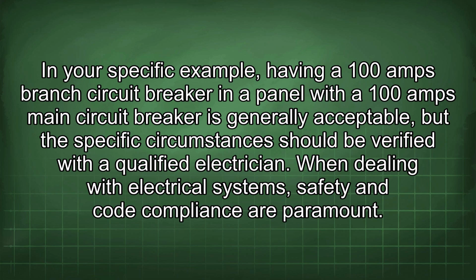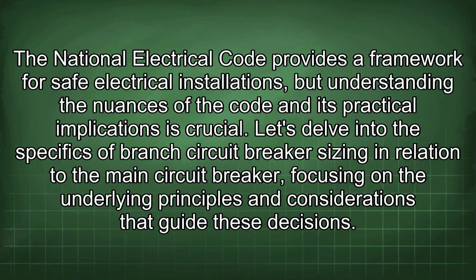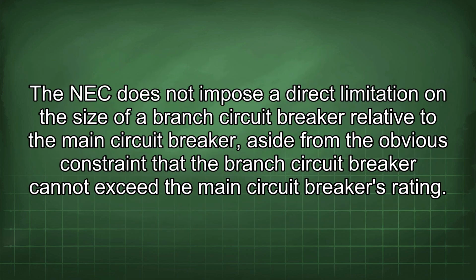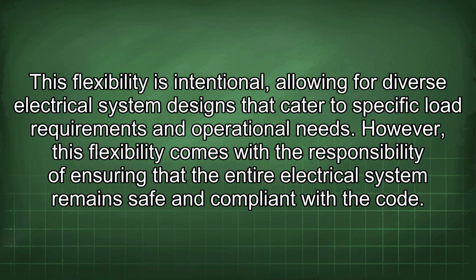When dealing with electrical systems, safety and code compliance are paramount. The National Electrical Code provides a framework for safe electrical installations, but understanding the nuances of the code and its practical implications is crucial. Let's delve into the specifics of branch circuit breaker sizing in relation to the main circuit breaker, focusing on the underlying principles and considerations that guide these decisions. The NEC does not impose a direct limitation on the size of a branch circuit breaker relative to the main circuit breaker, aside from the obvious constraint that the branch circuit breaker cannot exceed the main circuit breaker's rating. This flexibility is intentional, allowing for diverse electrical system designs that cater to specific load requirements and operational needs.